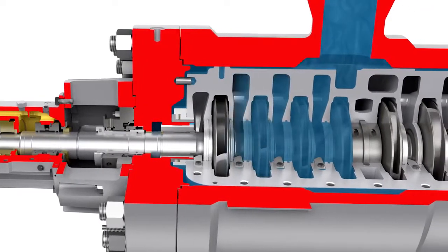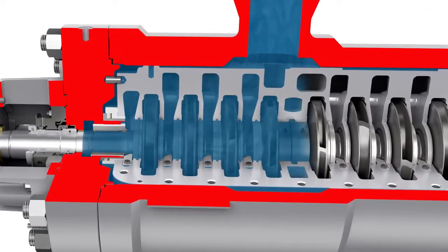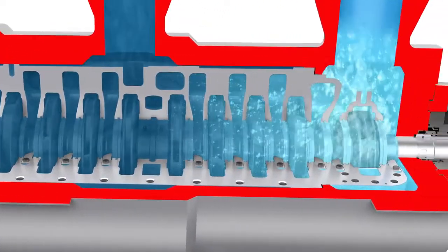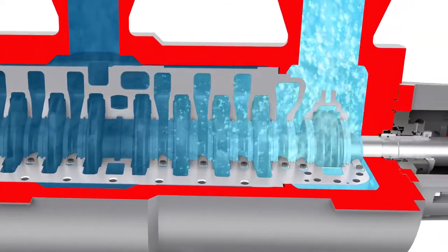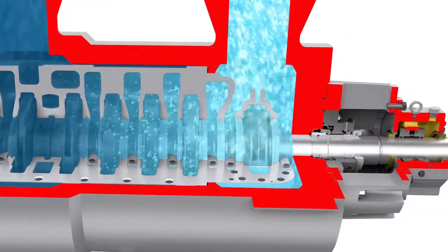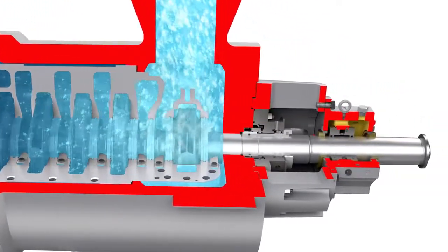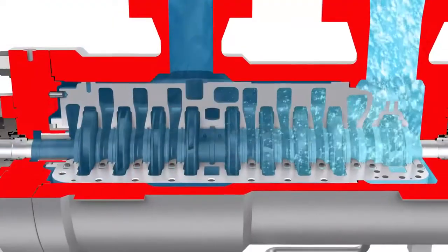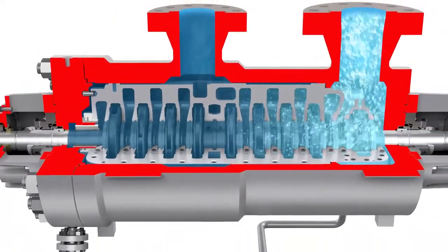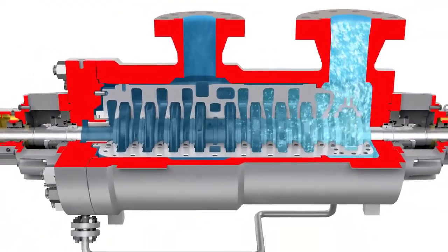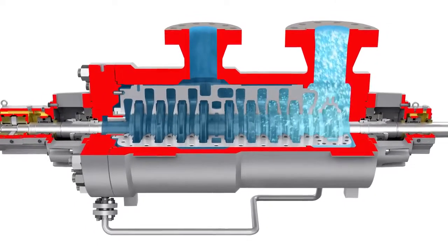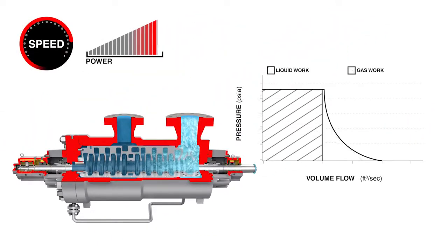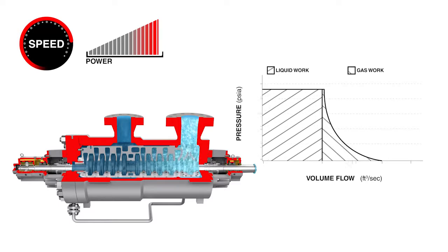However, effluent streams from reactors are not always single phase. Vapour evolves from the liquid as the pressure of the fluid stream drops across the HPRT. By volume or gas void fraction, the amount of vapour at the turbine's outlet pressure can be quite substantial — 60% by volume or more. In these scenarios, there is an additional recoverable amount of energy in the evolved gas.